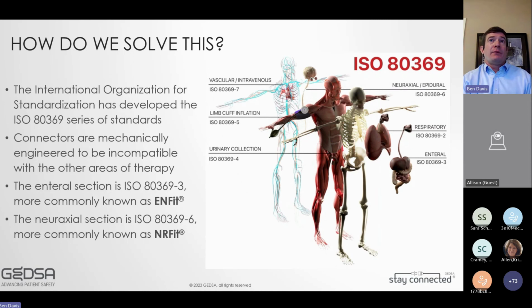While we're here, just to show you, the other sections are -7, which is the IV, basically. Interestingly enough, we just talked about the Luer, and it's a great connector. We don't want to abandon it. So it's actually the connector that's in -7. As part of this ISO standard, some of the criteria and wording have been harmonized to fit in with the other standards. But if you're using a Luer syringe, which you most likely are, you're using a connector that's part of the same series.